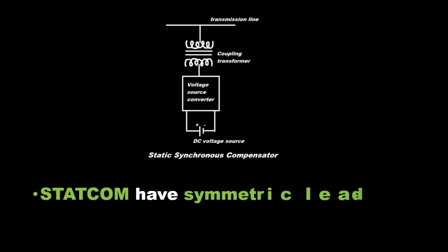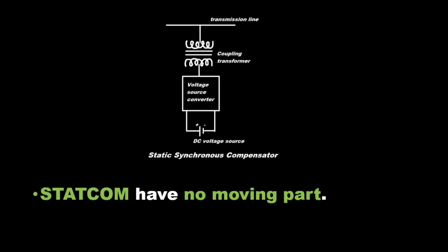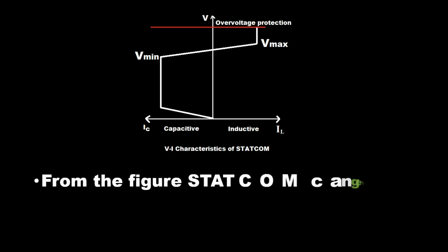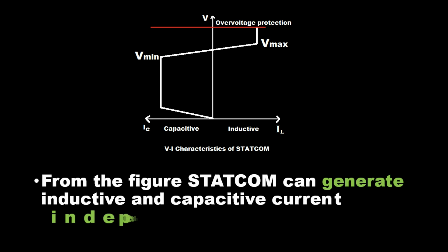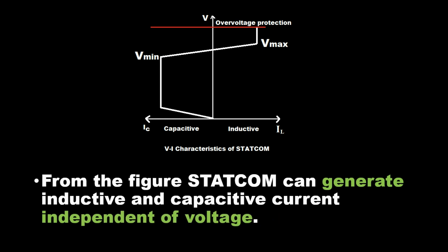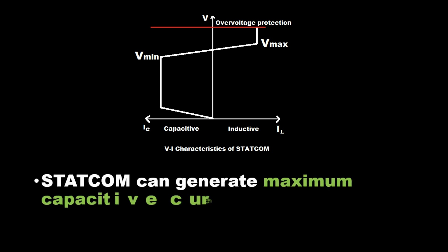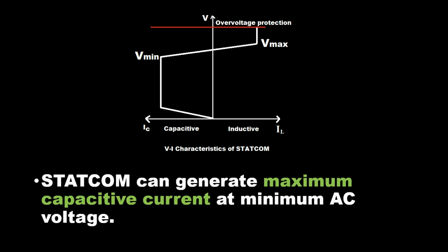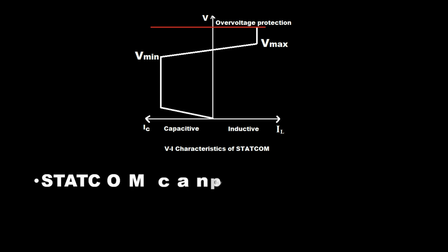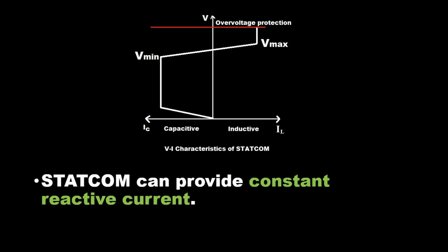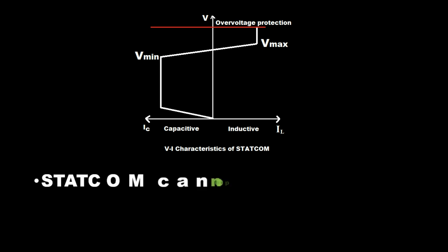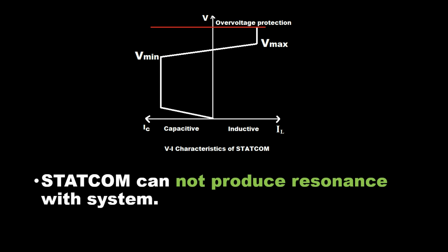STATCOM has symmetric lead-lag capability and no moving parts. It can generate inductive and capacitive current independent of voltage, and can generate maximum capacitive current at minimum AC voltage. STATCOM can provide constant reactive current and cannot produce resonance with the system.